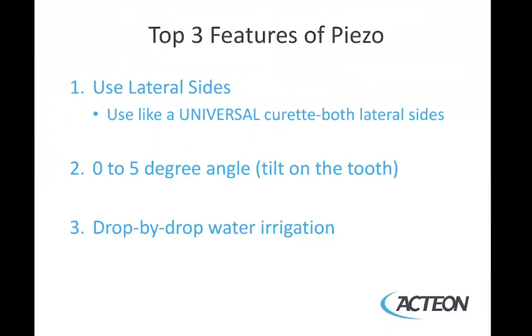The third unique feature is drop by drop water irrigation. Because the coolant is cooling the crystals in the handpiece, which do not generate the same amount of heat as the ferromagnetic rod stacks on Cavitron-type and magnetostrictive systems, you need about 50 percent less water.